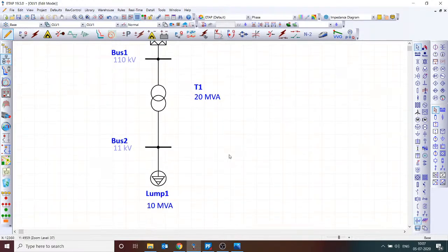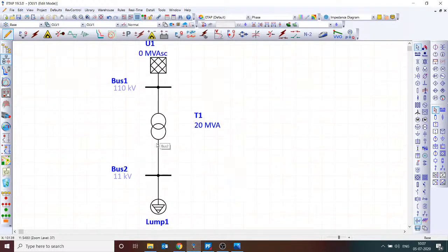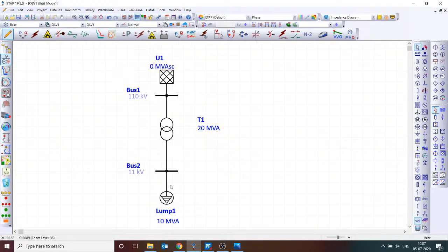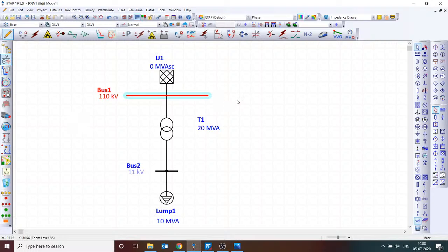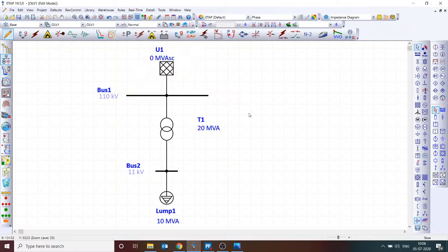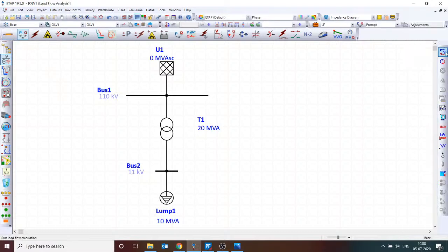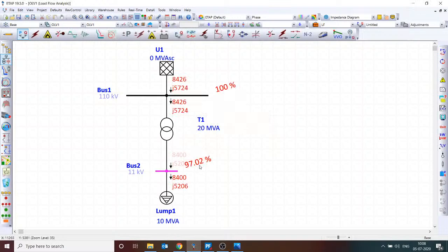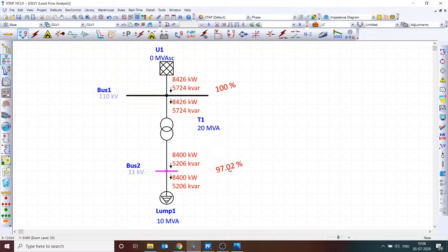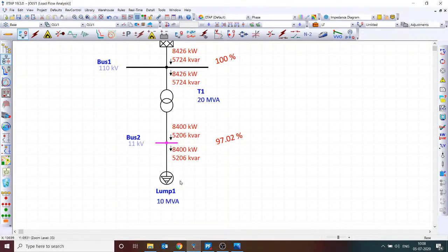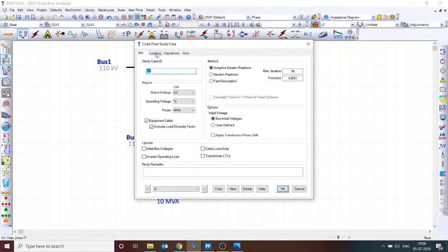The maximum demand is 10 MVA and minimum demand can go down to 2-3 MVA. Bus 1 is the 110 kV substation near the industry, which might be feeding many other loads and interconnected with many other substations. So the question is: how do we select a swing bus and whether the slack bus concept is applicable? The answer is yes — the slack bus concept is perfectly okay here, because a strong transmission system is feeding a small distribution system.